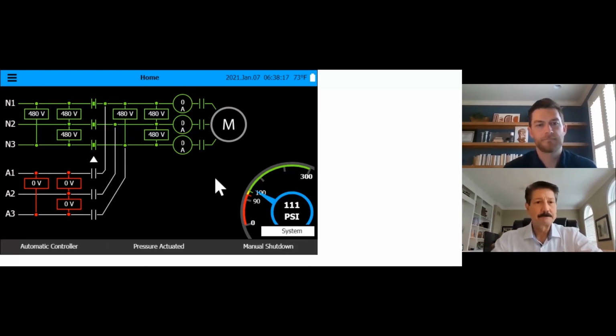Taking a look at the screen here, here's what we've got. Left side, N1, N2, N3. That's normal power. Immediately, per code, we need to show the voltage. What we're showing here is 480, 480, 480, between N1 and N3, which is phase A and C, or from A and B and C, or I should say B and C, we've got 480 volts. This is the line voltage right here on the far left side. As we move across to the right, we see a couple of contacts that are vertical. These are closed contacts, of course. Those are the breakers themselves, the isolation breaker and the magnetic breaker.